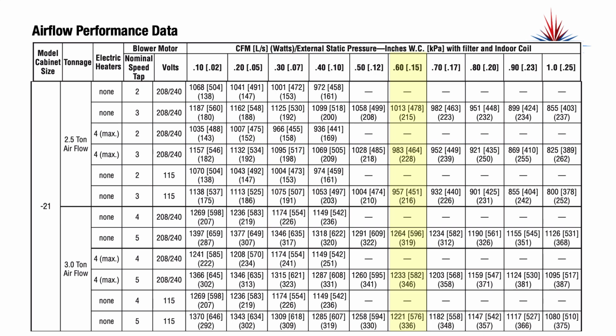If something changes, if a filter gets clogged, all of a sudden my static pressure goes up and my airflow is going to be too low. If I'm on a 3-ton unit with that static pressure, I'm fine, because I'm going to be above that 1200, but I won't be too high. I'm going to be about 1264, but I'm not going to have too low of airflow. So 0.6 will work for both sizes. Do I want it for a 2.5 ton? Not really. I'd rather be 0.5 and under.